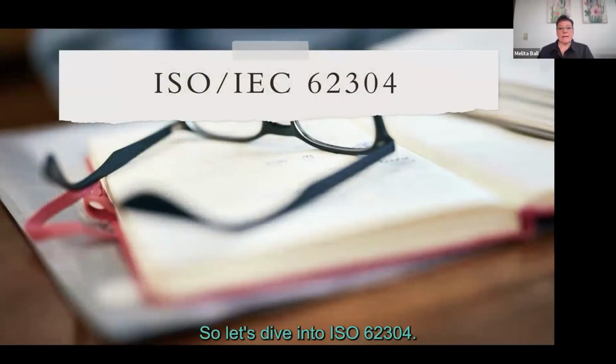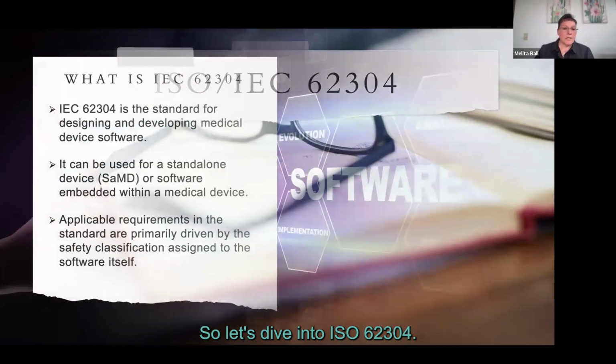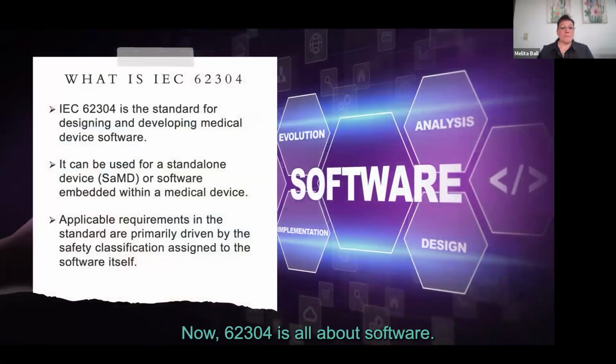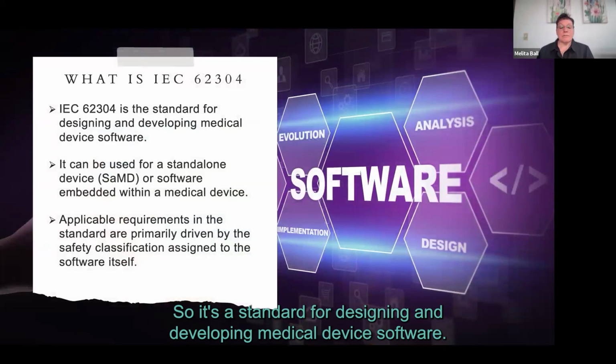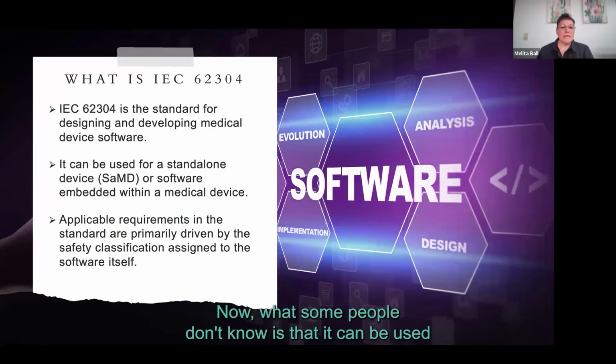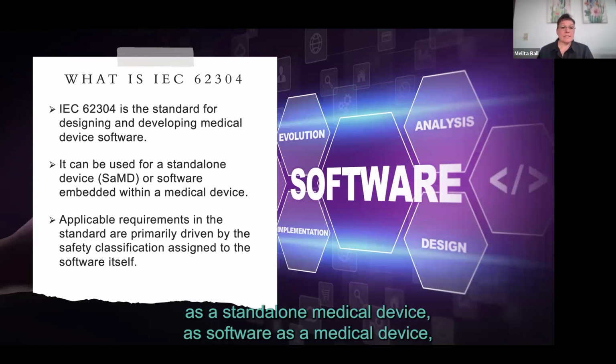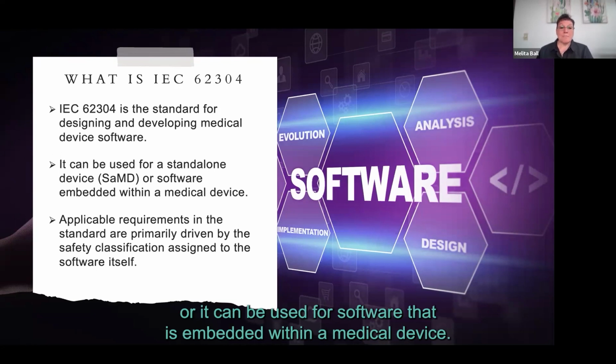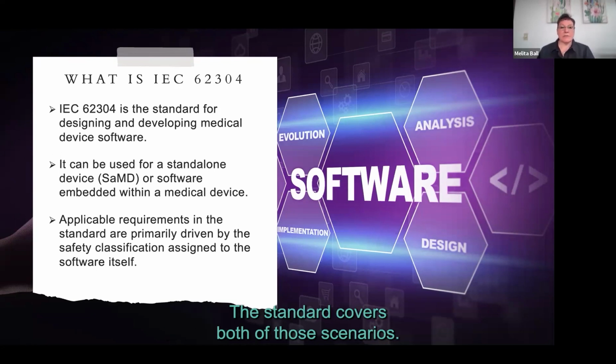So let's dive into ISO 62304. Now, 62304 is all about software. So it's a standard for designing and developing medical device software. Now, what some people don't know is that it can be used for a standalone medical device, software as a medical device, or it can be used for software that is embedded within a medical device. The standard covers both of those scenarios. The same standard can be used for both of those scenarios.